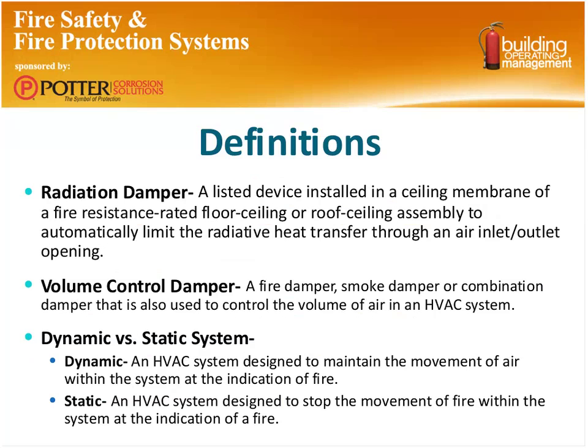A radiation damper would be a typical damper that goes through a fire-rated assembly. It really has no true airflow, but the damper is intended to close some kind of an opening in a rated floor or ceiling assembly. A volume control damper, well, that's pretty self-explanatory. It's controlling the flow of air.